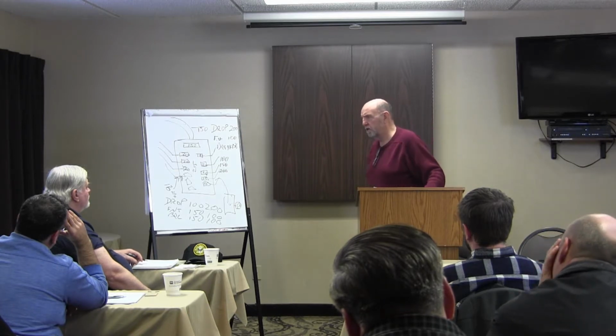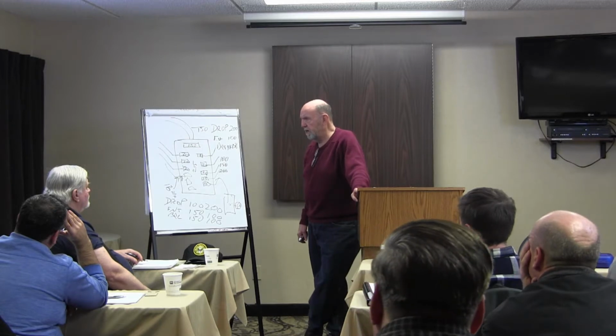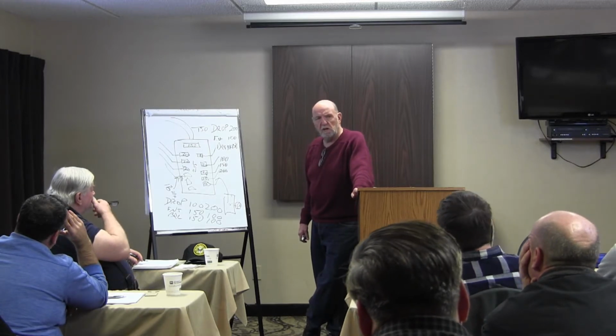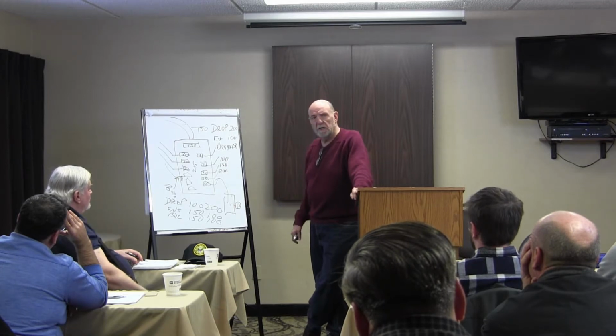What if there's conduit running down the house and you can't see the wire size going into the meter? Well, it depends on who you're talking to. Jamie assumes it's going to be lower and calls that out as a defect. It's also invisible. I don't think you can call that out as a defect. If all I see is the main breaker because it's all in conduit, then that's my service size.